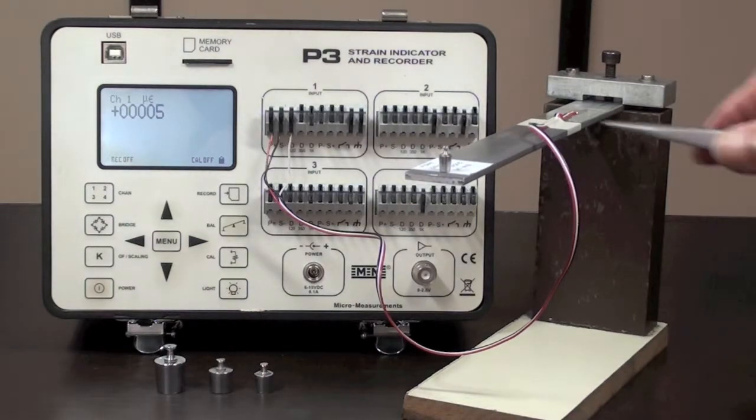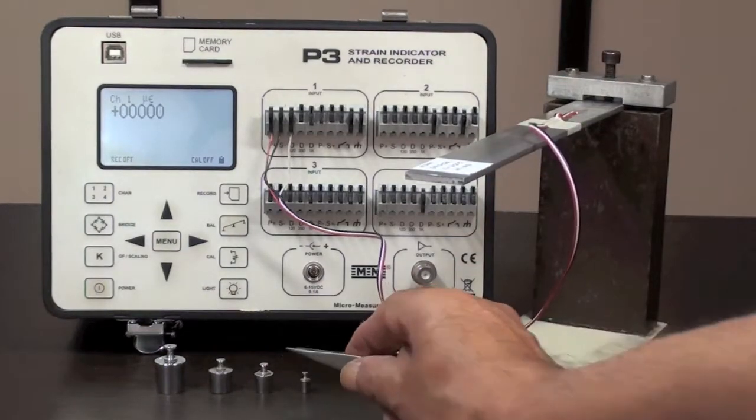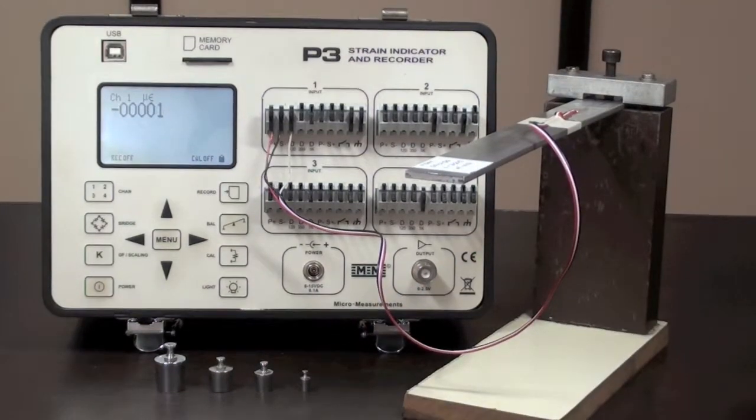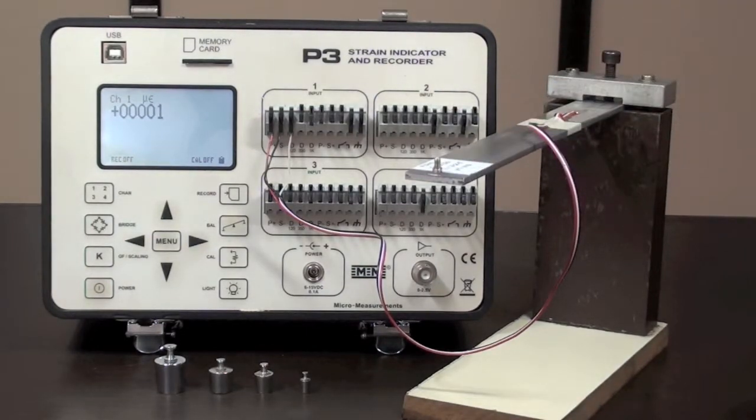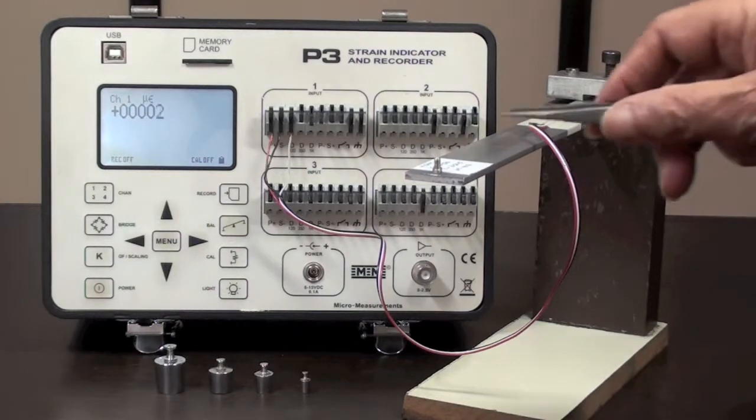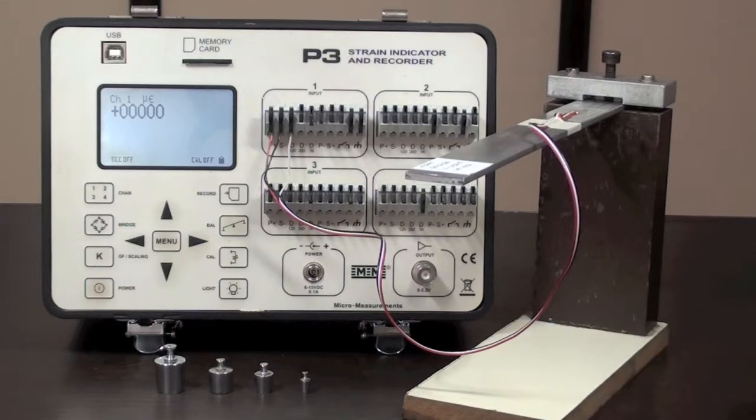Smaller weights on the beam weighing less than 1 gram show readings down to 0.1 microstrain and it appears that the strain gauges are far more sensitive. The onus is on the readout instrument to resolve and display fractions of a microstrain. But for this, it is important to have a gauge installation of very high quality and a very stable and accurate strain measuring instrument.